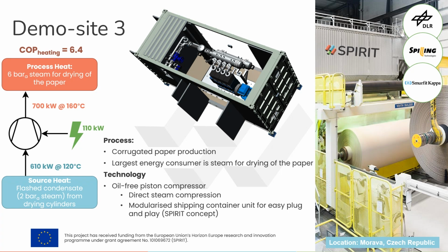After the steam goes through these cylinders, it's condensed, and can be used as a source of heat for the heat pump. So we will flash the condensate to produce steam at 2 bar, and we'll upgrade this in temperature level to produce 6 bar steam, which can be reused for drying the paper.